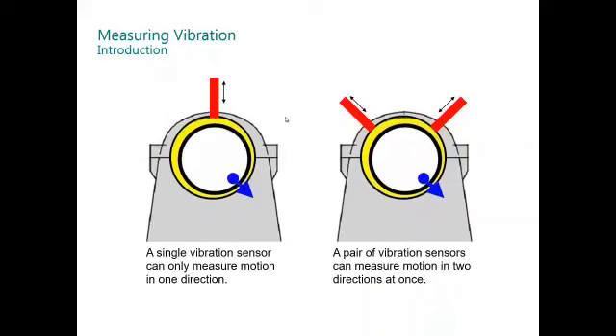To measure vibration, the transducers have a direction or sensitive axis for measuring vibration. On the left, there is one vertical transducer, and on the right, there are two transducers located at 45 degrees from the vertical direction, separated 90 degrees apart between them to measure the total vibration in the plane.